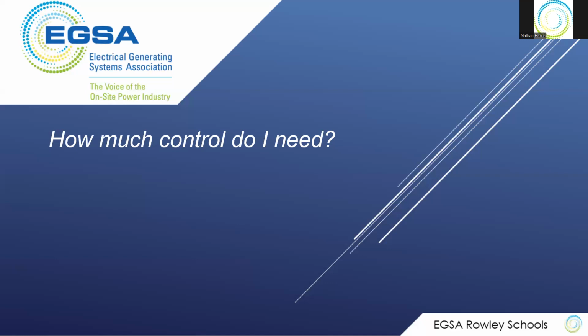So there's control systems with galvanic isolation, and then the power system with this grounding system, 2 different types of considerations. But the galvanic isolation that I'm talking about now has to do with the control system. You do have isolated grounds, like hospital grounds, building grounds. You may have a generator feeding 2 different buildings, and they want to put a ground rod at each building. Well, that's not a real good plan, okay? Unless you have one generator, because the generator wants to be grounded. So that's another form of isolation required. I'm talking more on the control system, galvanic isolation, little voltage signals and little control signals. So hope that helps.